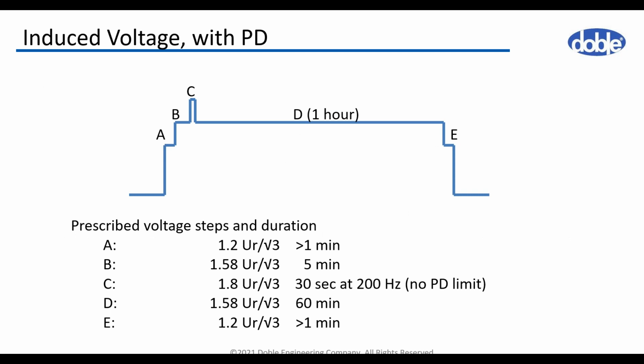This is how the test sequence of the induced voltage test with partial discharge measurements looks like. The first part of the measurement is the measurement of the background level, which is performed at 0.4 multiplied by the rated voltage. It should be less than 50 picocoulombs.